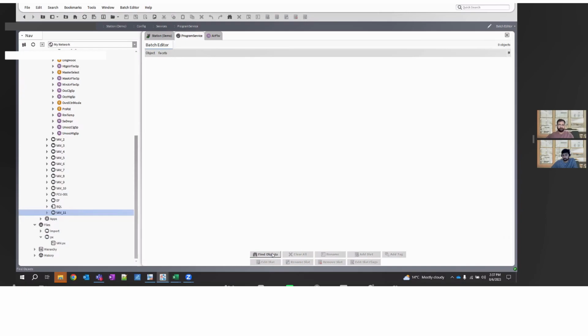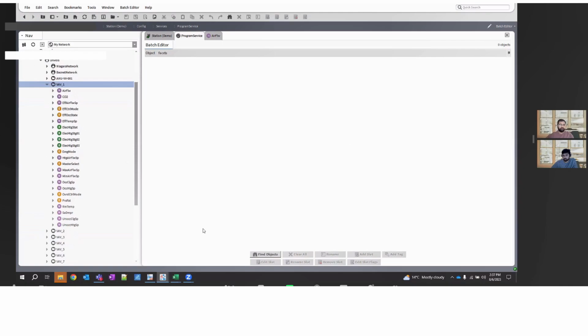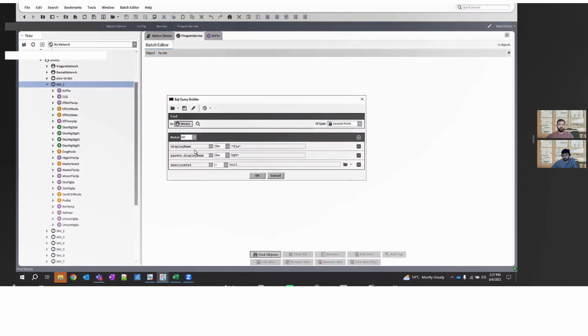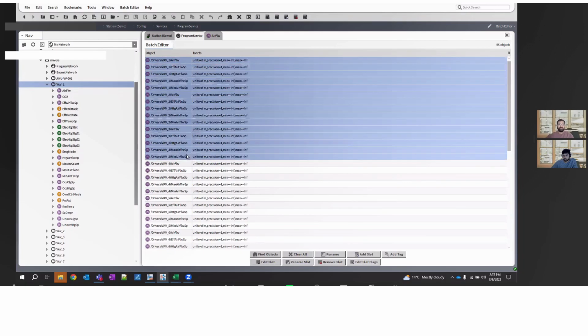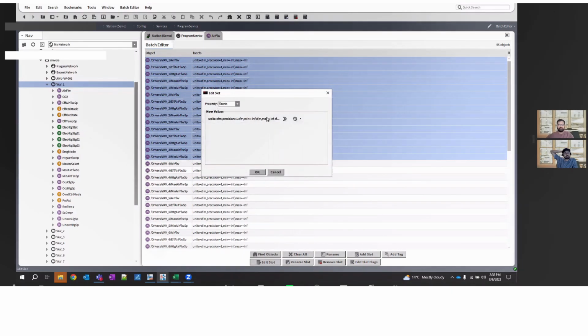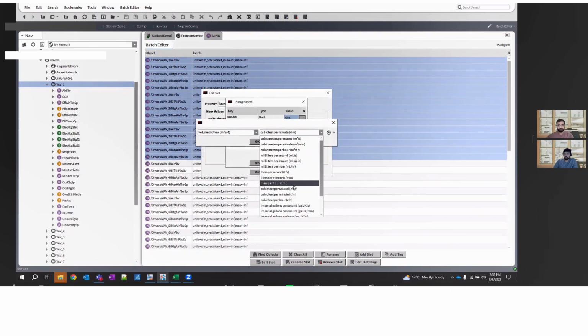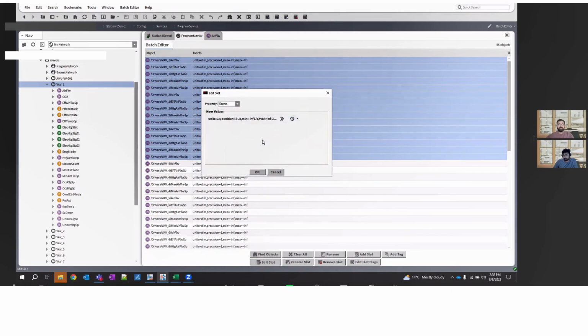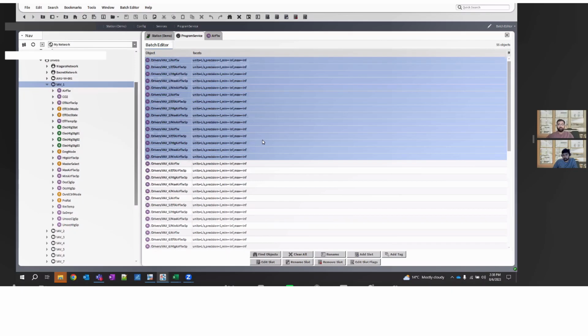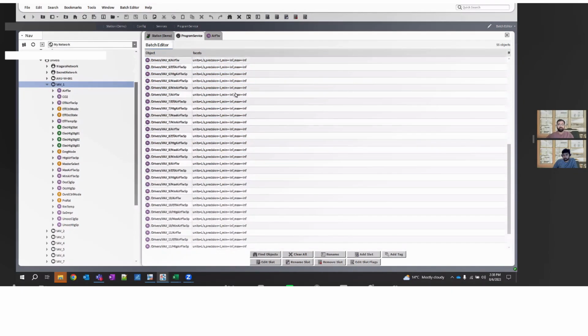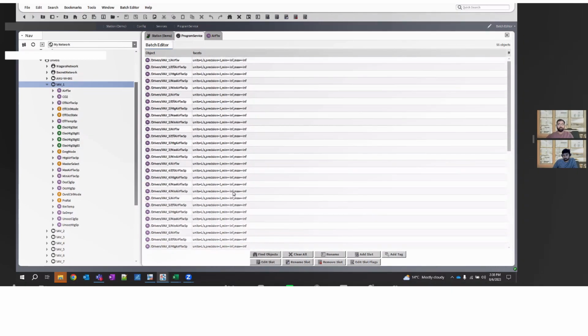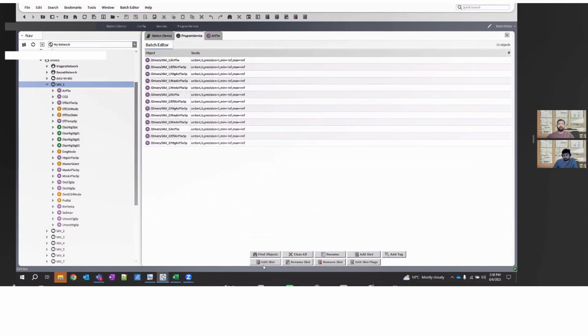One thing to note, whatever points appear, I'll give you another example. I've seen a lot of people make this mistake. They assume that the points they are selecting will only get impacted in the program service, and they make the changes, let's say change the unit to liter per second again, assuming only the selected points will change and the rest remain as is. However, what you'll notice is all the points or components that were part of the program service discovery will have their units changed. So whatever components you don't need, delete them from the program service before making the required changes.